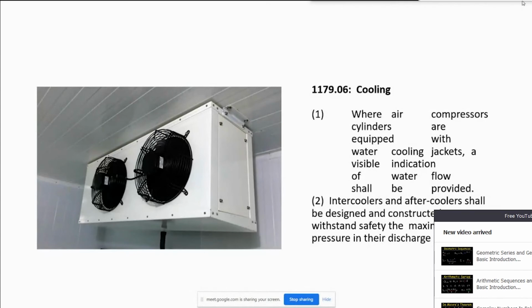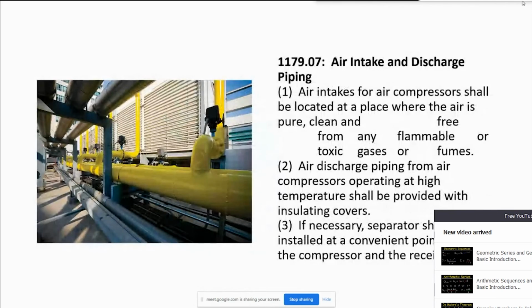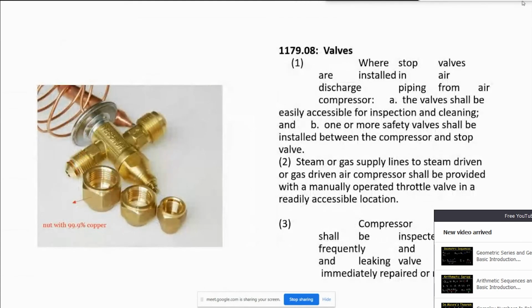Intercoolers and aftercoolers shall be designed and constructed to withstand safely the maximum pressure in their discharge piping. Air intake and discharge pipe. Air intakes for air compressors shall be located at a place where the air is pure, clean, and free from any flammable or toxic gases or fumes. Air discharge piping from air compressors operating at high temperature shall be provided with insulating covers. If necessary, separators shall be installed at a convenient point between the compressor and the receiver. Valves. Where stop valves are installed in air discharge piping from an air compressor, the valves shall be easily accessible for inspection and cleaning, and one or more safety valves shall be installed between the compressor and stop valve.